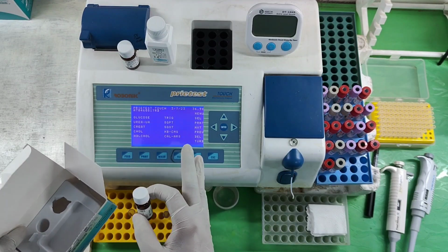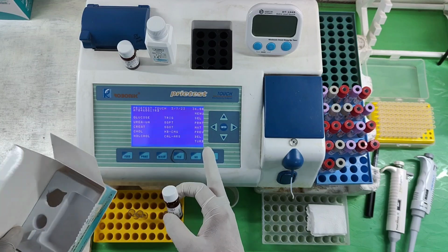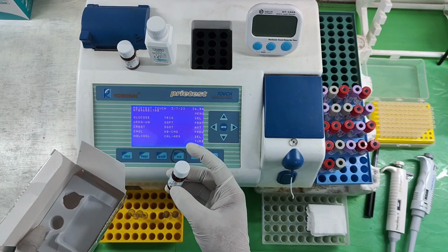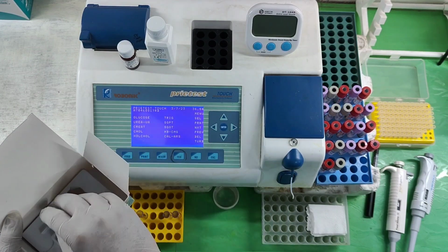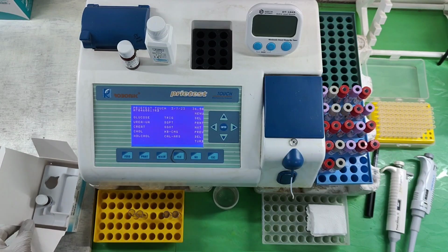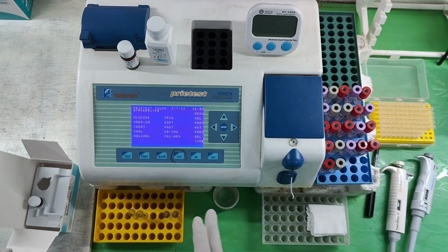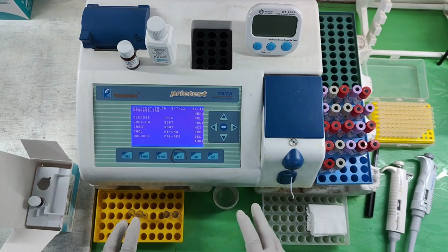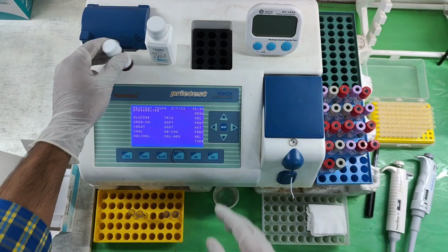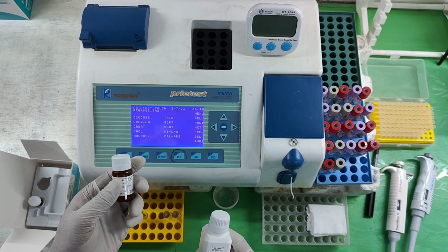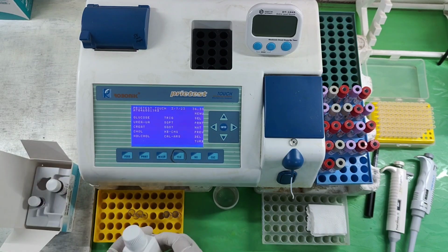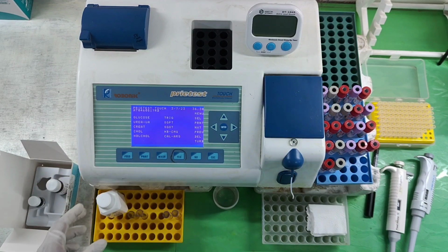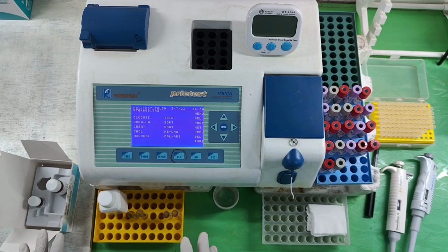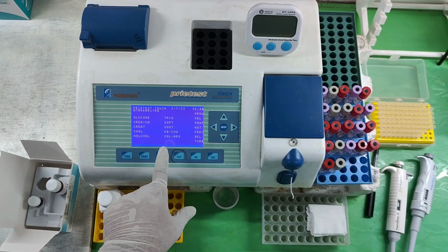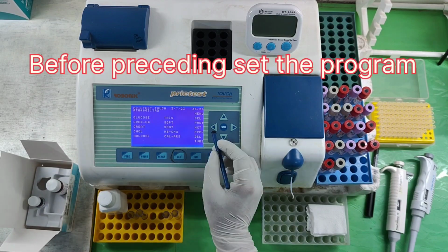I have already calibrated the RA factor test in this machine. That's why there is no requirement of calibration at this time. I am just going to show you the method of estimation of RA factor. This is reagent 1 and this is reagent 2. Before performing this, I am going to set RA factor in this machine.